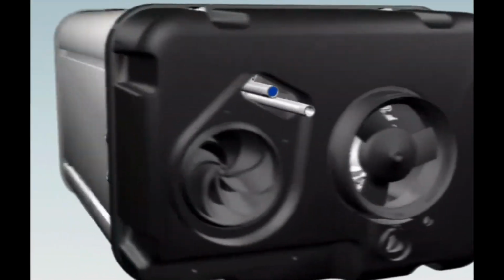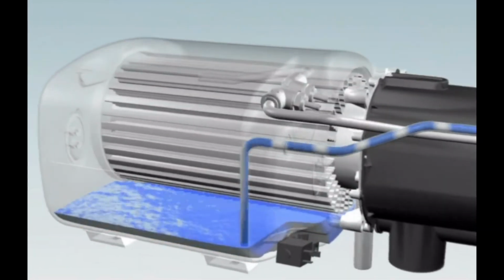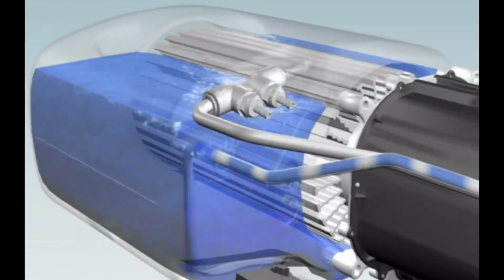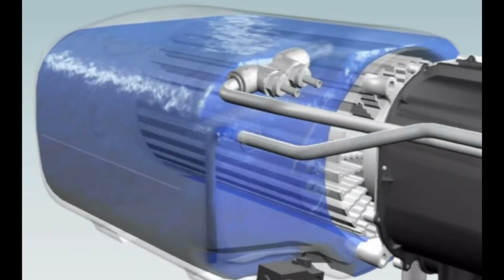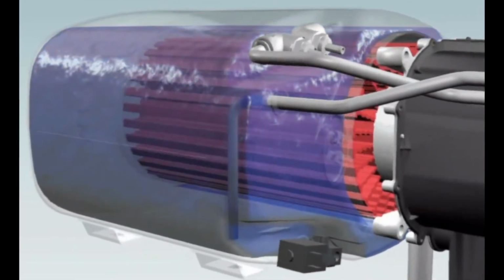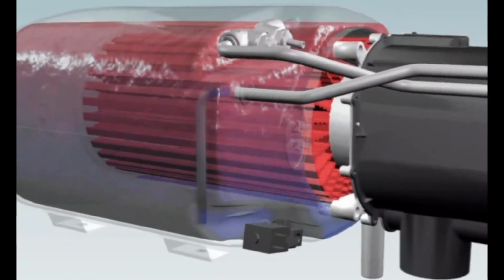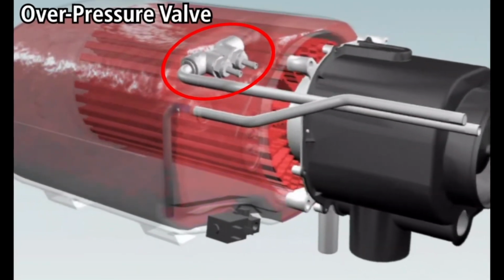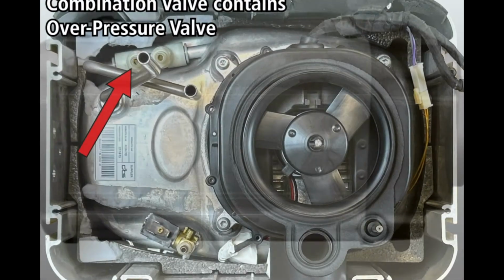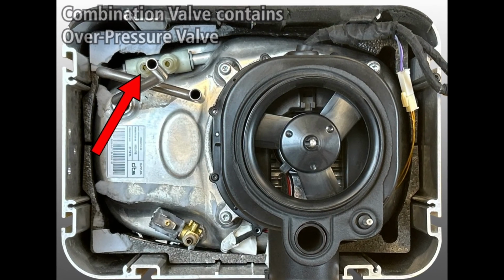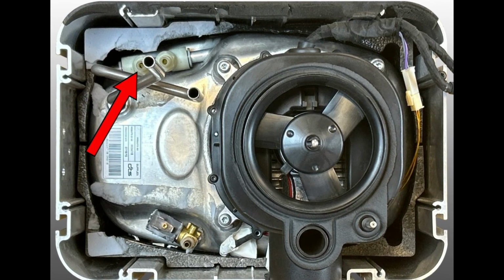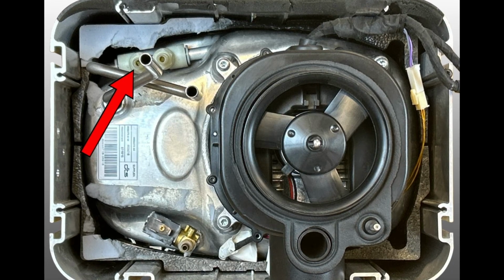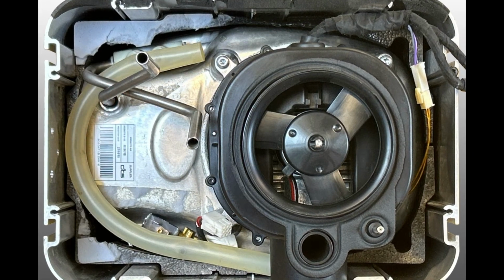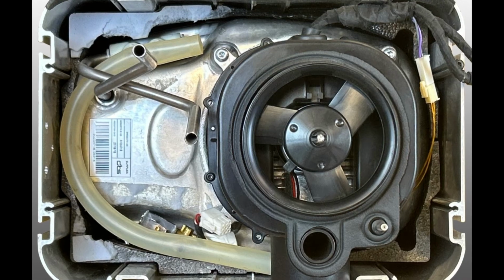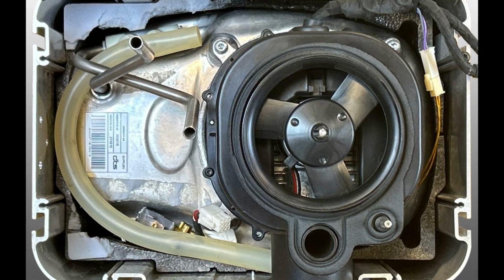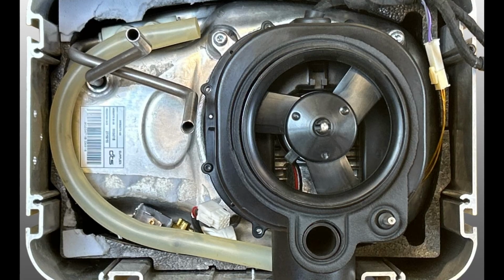As water is heated, it expands. This can cause water to leave the boiler via the overpressure valve, part of the combination valve. This will amount to no more than a few drips every time the water is heated. We can see the overpressure valve in the upper left corner of the heater. The heating air blower motor and the drain tube have been removed for clarity. The overpressure valve expels water into the drain tube that then drips onto the ground. During normal operation, a little water will accumulate under the heater as the water expands every time it's heated.